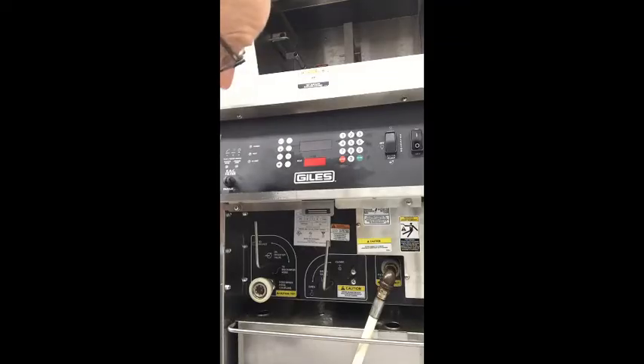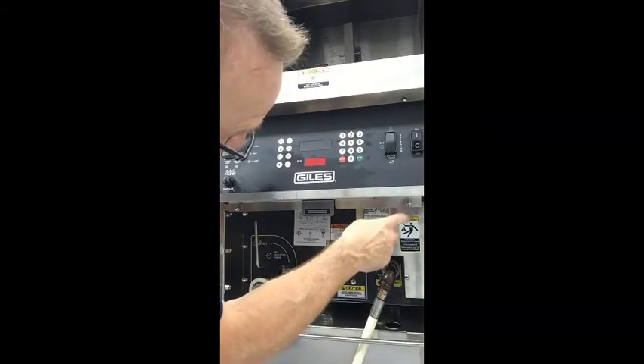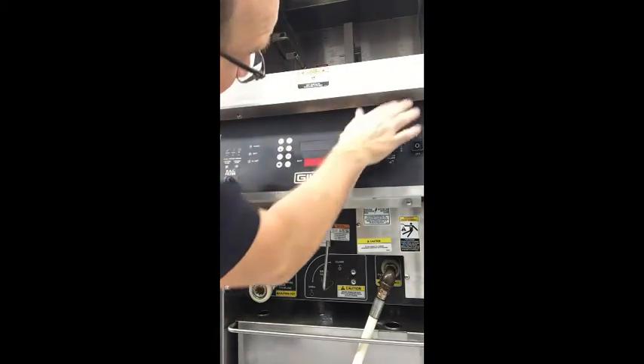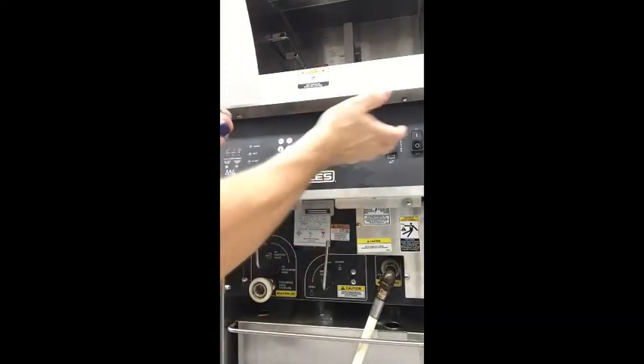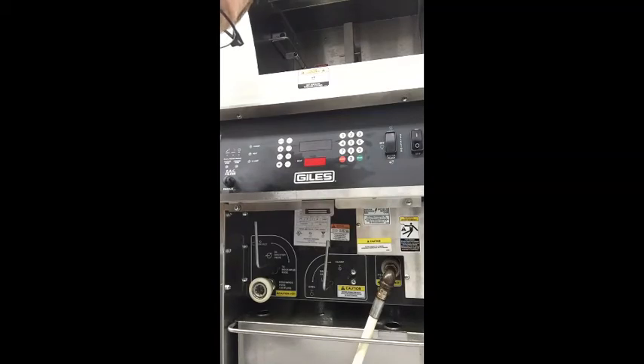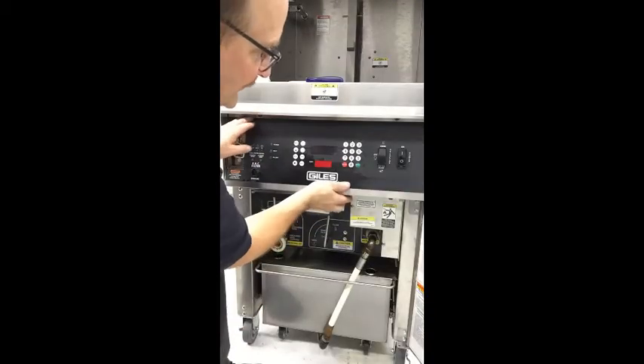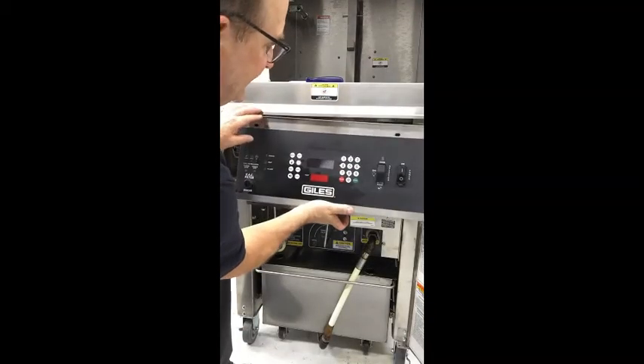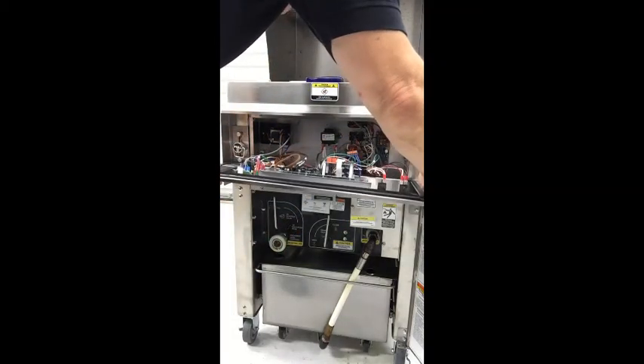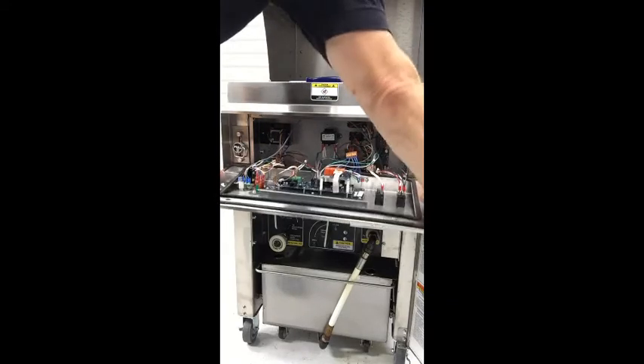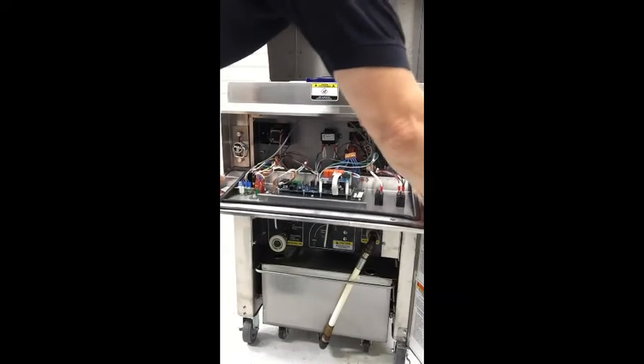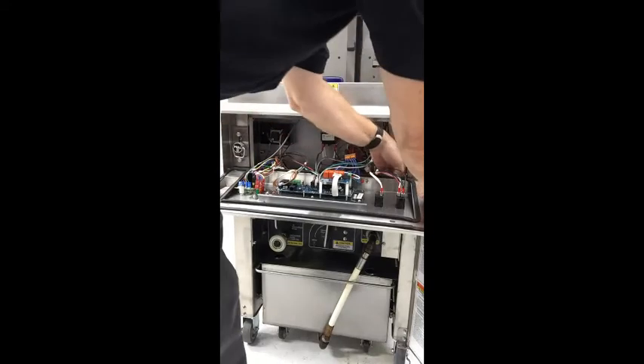Now let's familiarize ourselves with the wiring on the controller itself on the rear side. Kind of give you a better layout and a good test point place. You've got four screws, four Phillips heads: one, two, three, four. Once we take those loose, we'll be able to drop this panel down, and then I'll show you how to hook that up. Once we've removed all the screws, the panel itself will slide down and drop down. Notice that you can take this panel and set it up on those little brackets, and then it'll sit right there, and that'll hold it in place while you work.